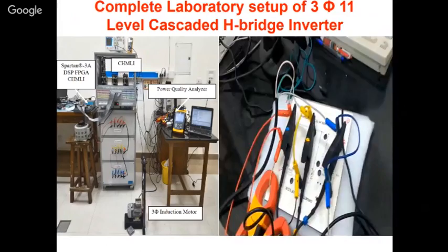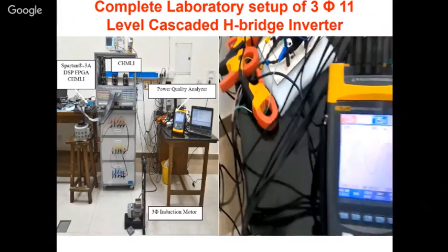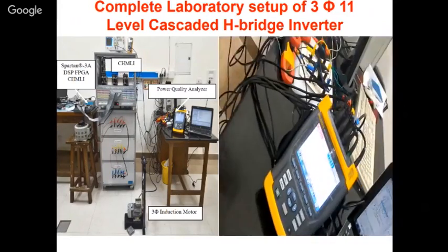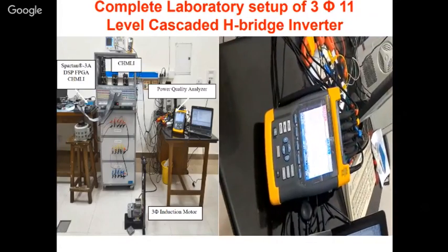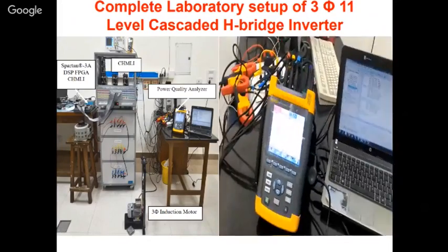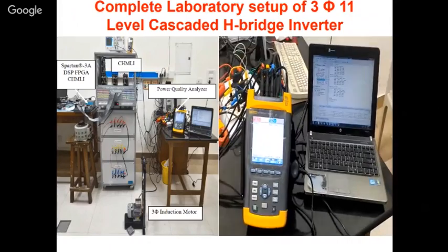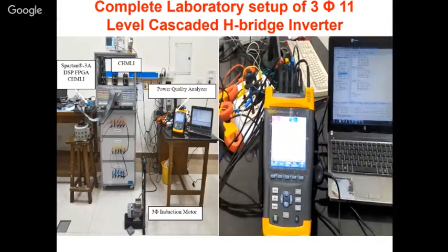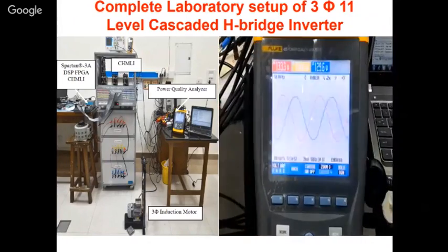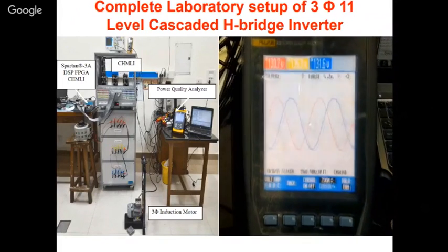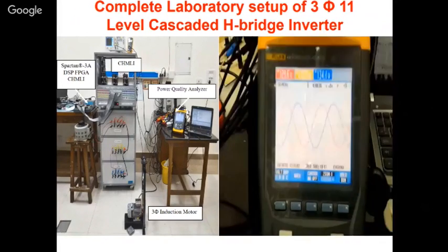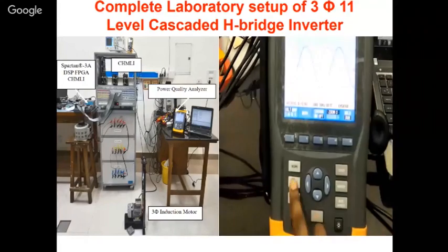You can see here the power quality analyzer, connected with the laptop. In the laptop software we can see all these things, and you can see the output voltage also, what steps you can get, the voltage 129, all these things, and we can measure the THD also.